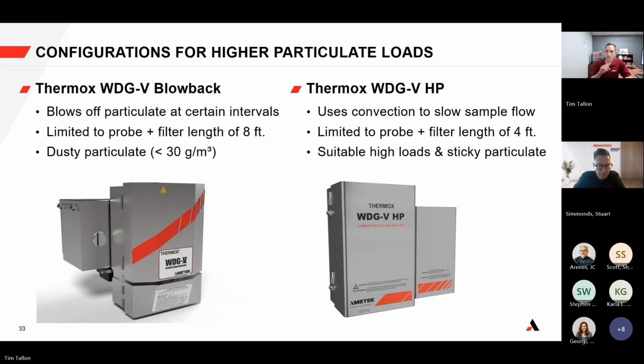Now the WDG-HP and the HP2, its predecessor, handle everything else - all the other particulate, all the other high loads, sticky particulate. While the WDG-V blowback has an aspirator attached, that's also pulling in particulate. It has a filter, but it's also drawing in and accumulating a lot of particulate potential on it as well. That's why it's important to have dusty particulate to make it easy to blow off.